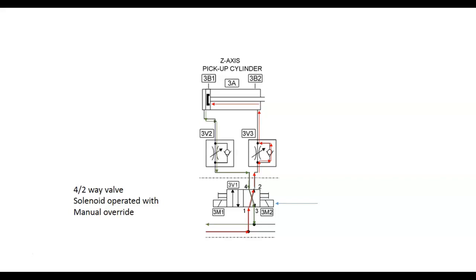So this is two solenoids. We not only use a solenoid to shift it to the right, we use a solenoid to shift it to the left, and it's drawn in its at-rest position. What you've got to do in your head is picture that right now this is pressure, so the fluid would be flowing out this way, bypassing this.